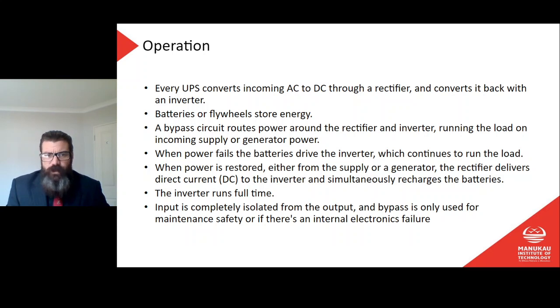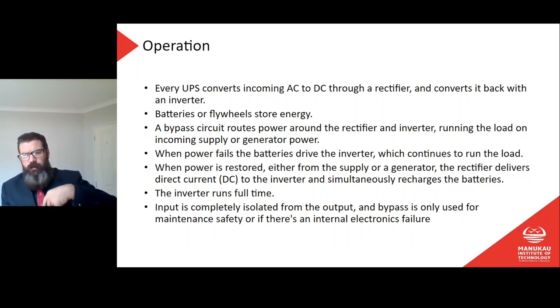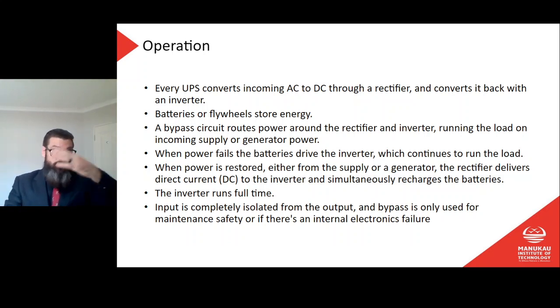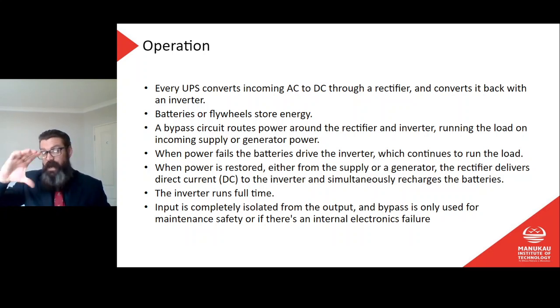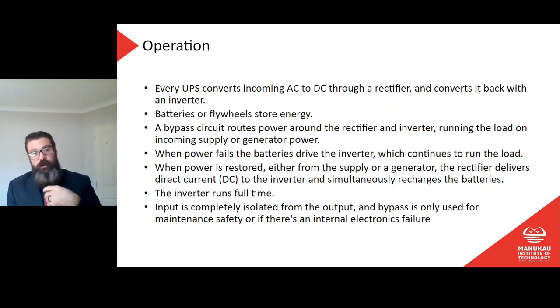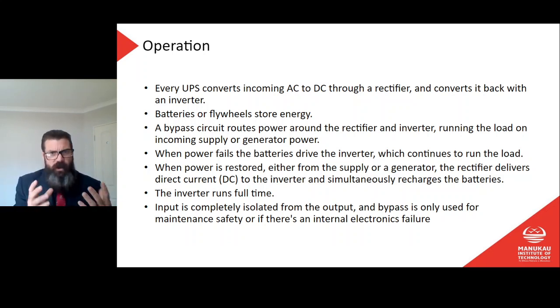Batteries or flywheels store energy. So the flywheel, I've never come across a flywheel UPS, but I guess such a thing exists. A flywheel UPS would be a motor running a big wheel with a lot of weight behind it, and it would just turn it over, and then when the power turns off, that wheel, if you've got a good balanced, big heavy flywheel, it can run for a while. So that flywheel would keep turning under its own steam, and then you could use that to power a generator, which would output some power. So that's the theory behind a flywheel UPS, although I've never seen one. I've never even heard of one.